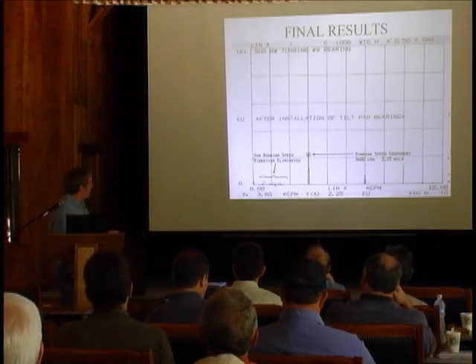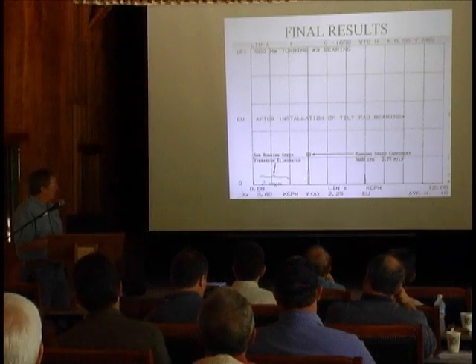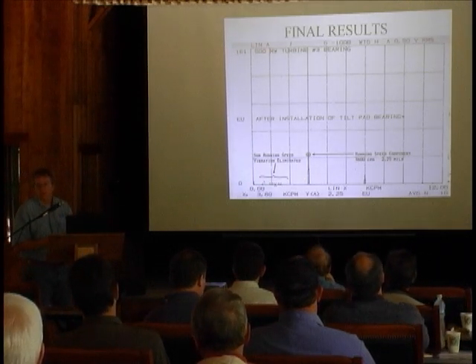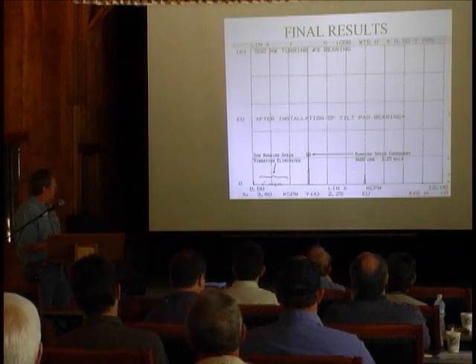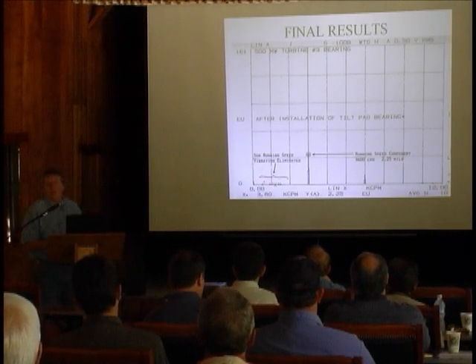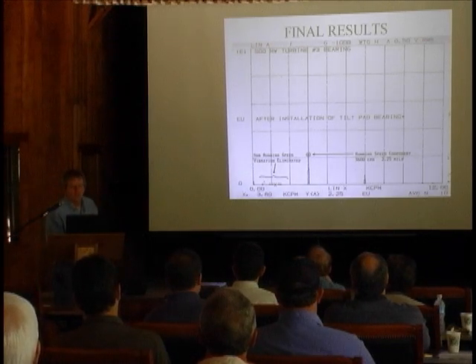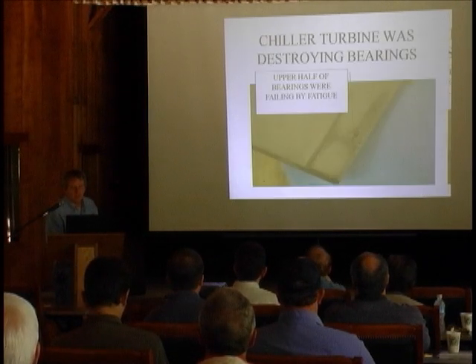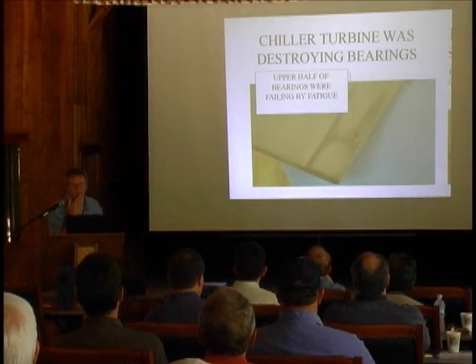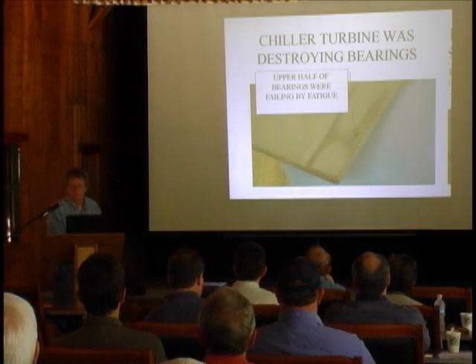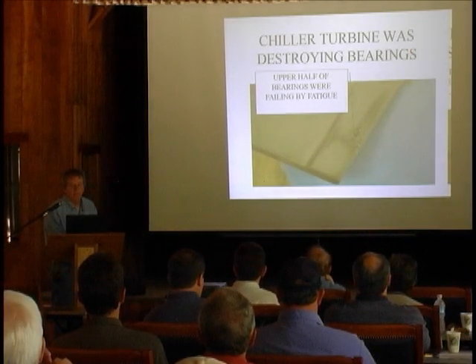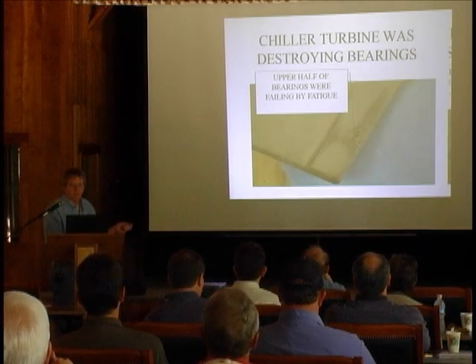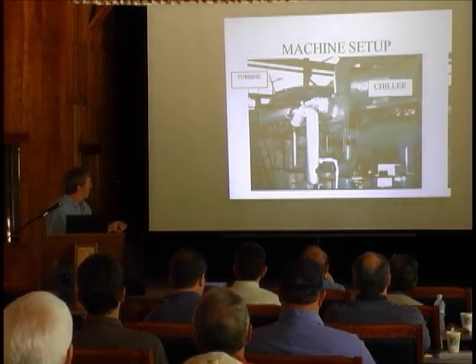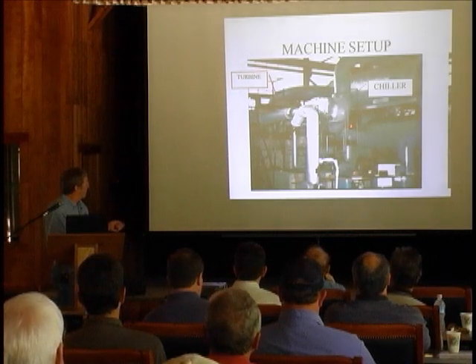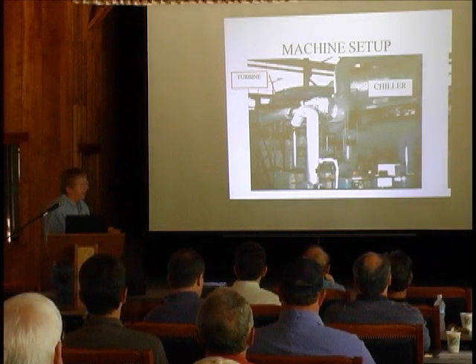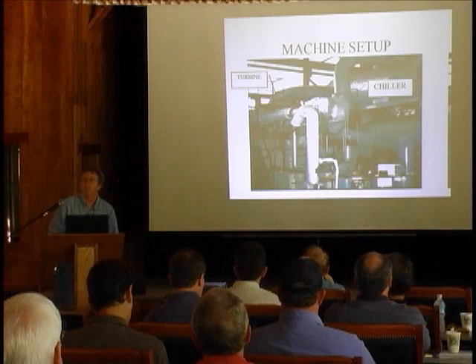And this shows you right here, running speed component went up a little bit because the tilt pad bearing has different damping characteristics than a regular bearing. But this sub running speed, it just eliminated it entirely. No longer did we have to deal with that. And I calculated the cost savings on that. I don't normally do that, but because we had about 2 or 3 of these incidents a year, it was horrendous. It paid for the bearing each time that happened. This is a chiller turbine, and it was destroying bearings. This is actually a chiller right here, and this is the turbine and the chiller. It was destroying bearings, and the odd thing, they were beating up the top part of the bearing instead of the bottom part.